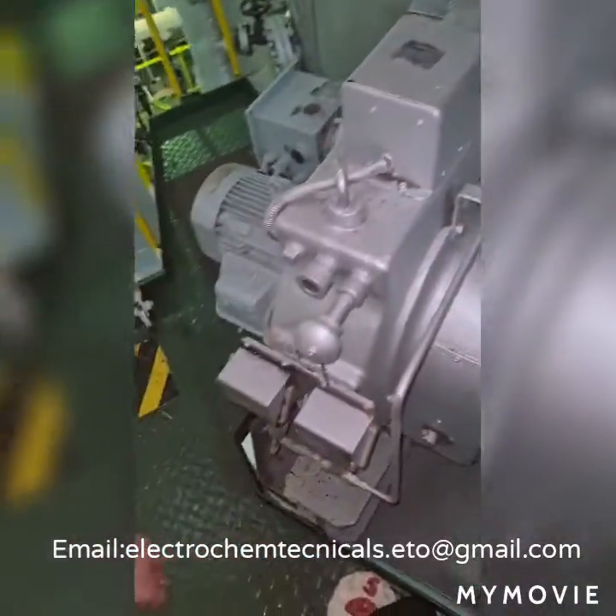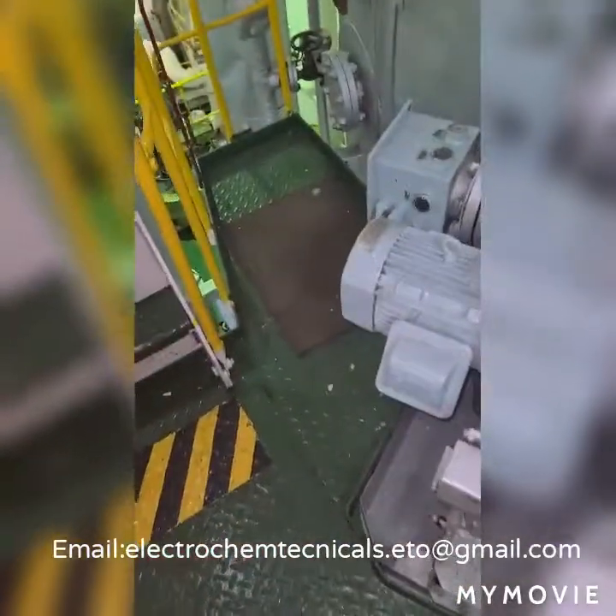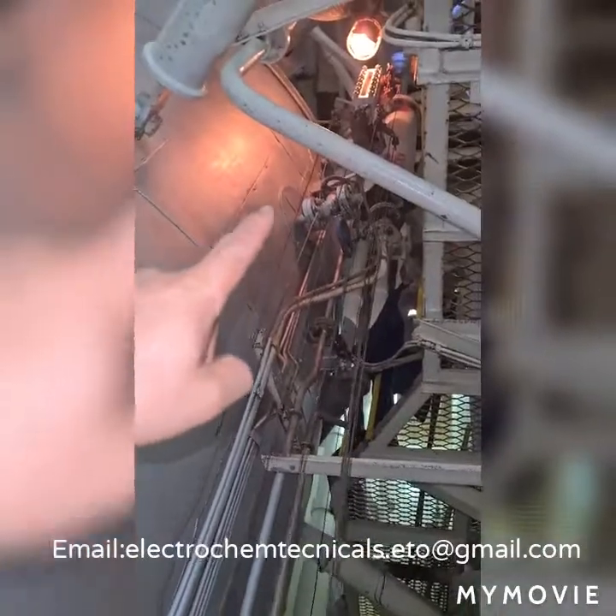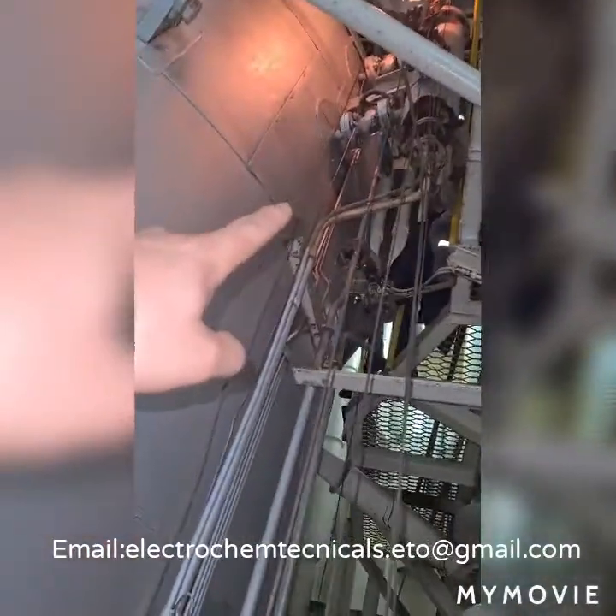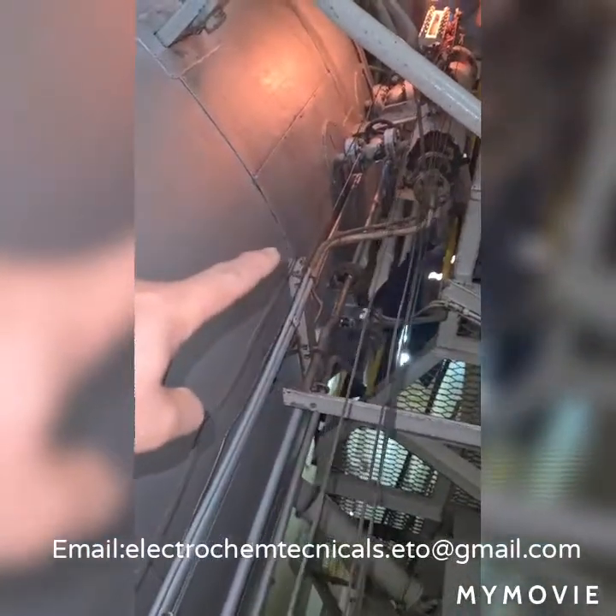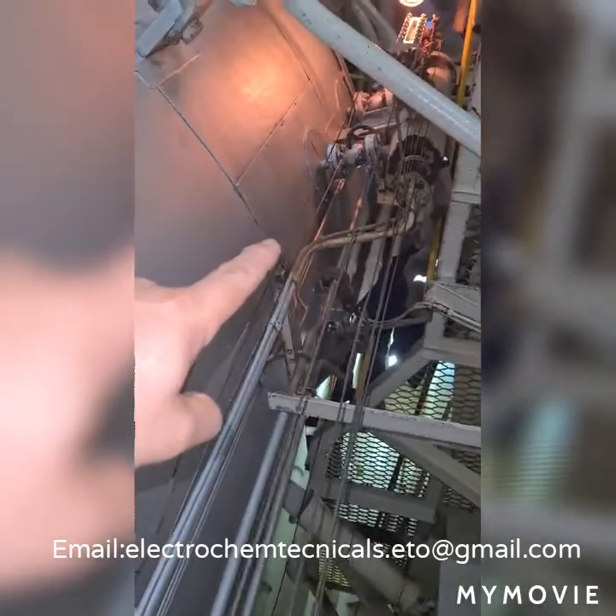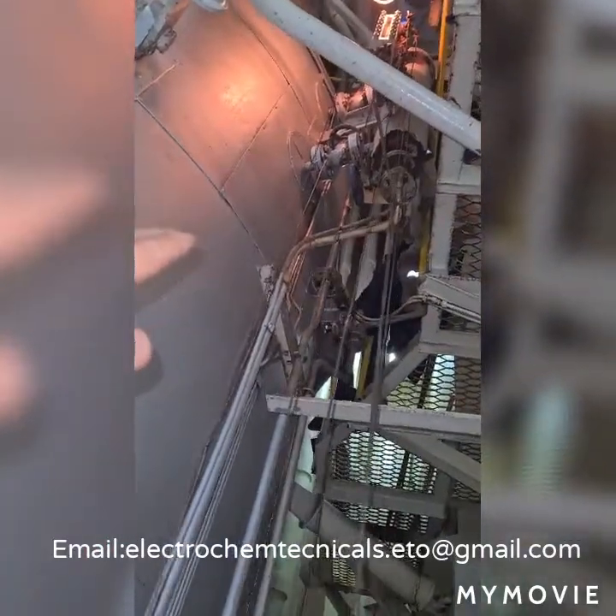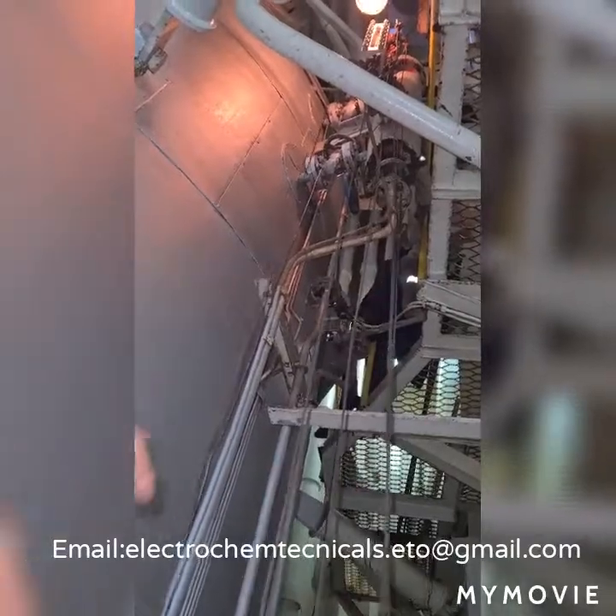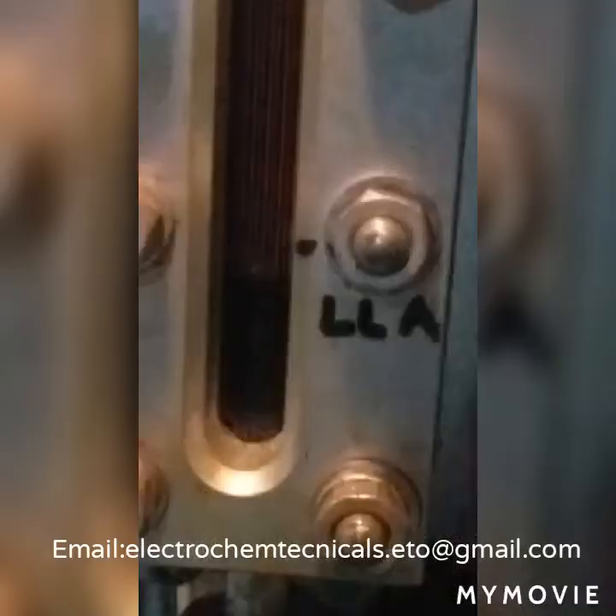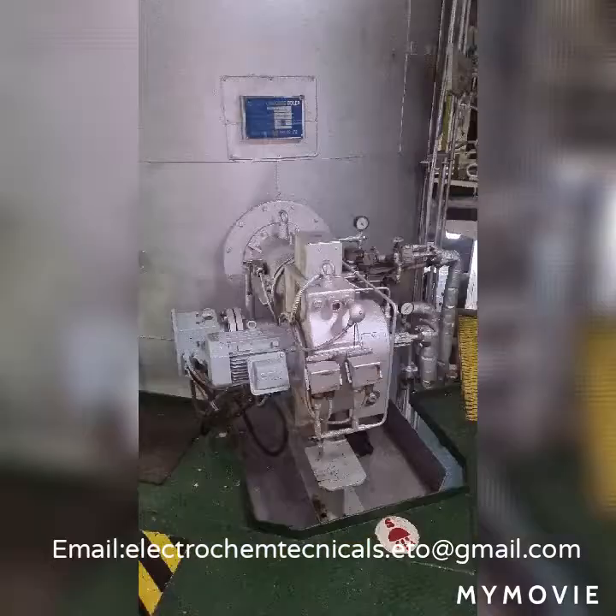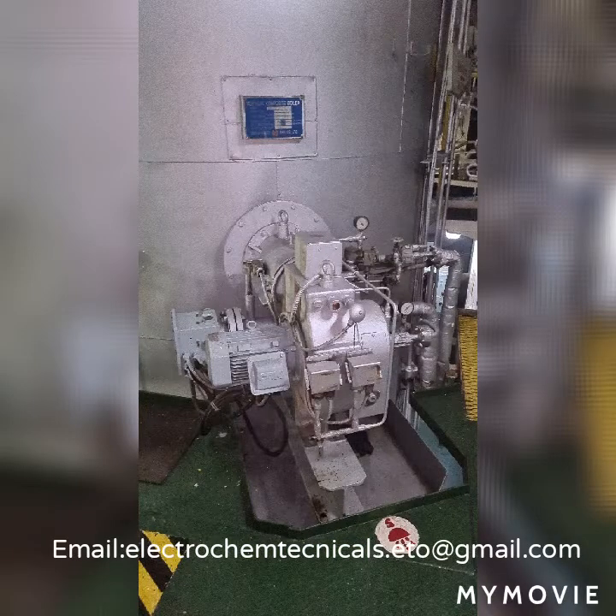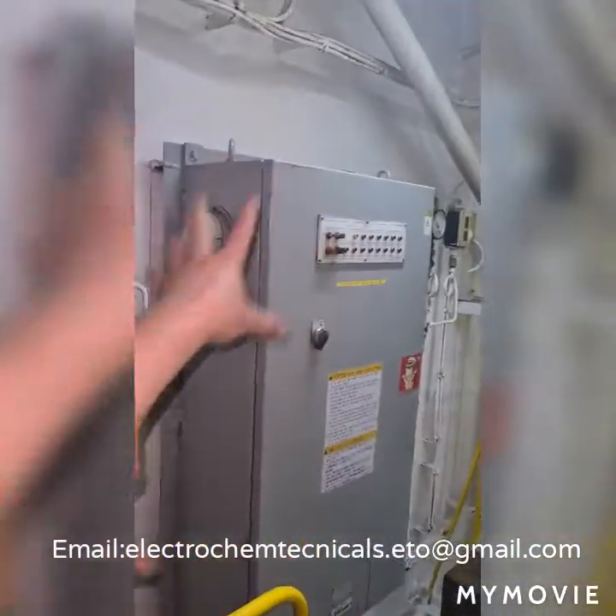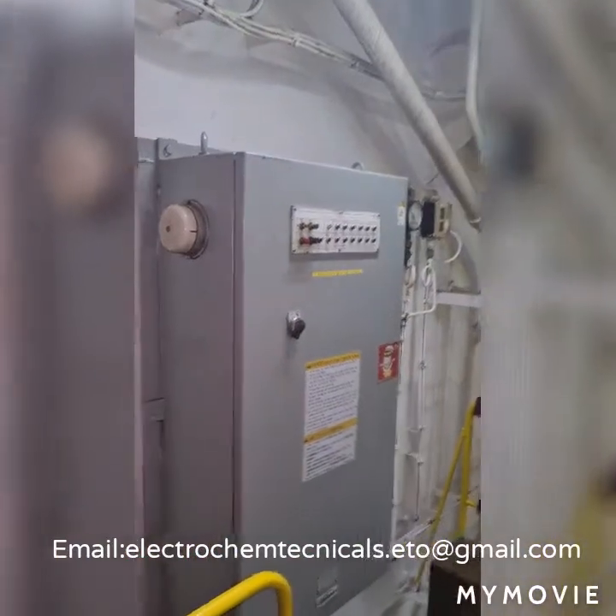And we have also the chamber here from which the water level sensor electrodes are sensing the high water, the low water, and the lowest water level alarm, and cut off the fuel flowing to the main burner by de-energizing the solenoid valve and stop the boiler from operating. And this is the entire control panel of my boiler.